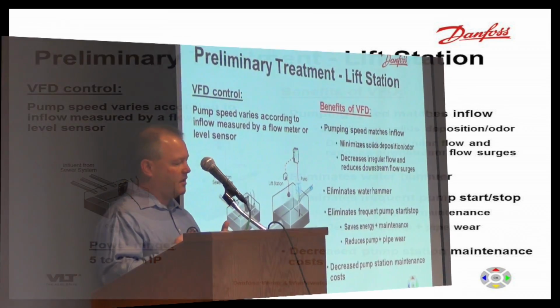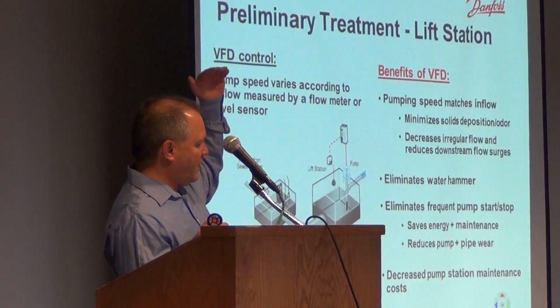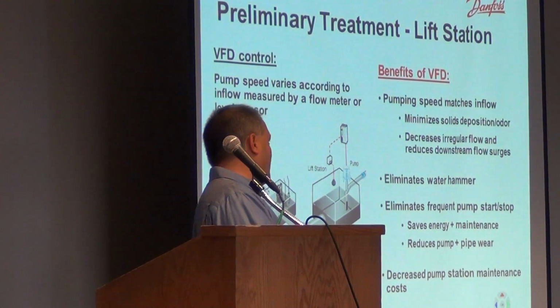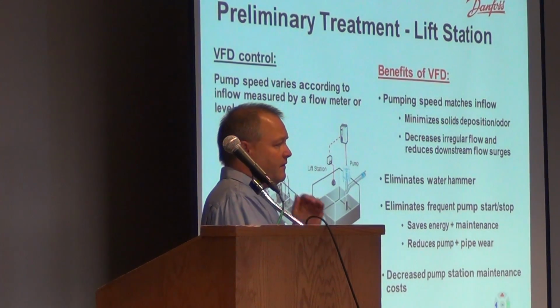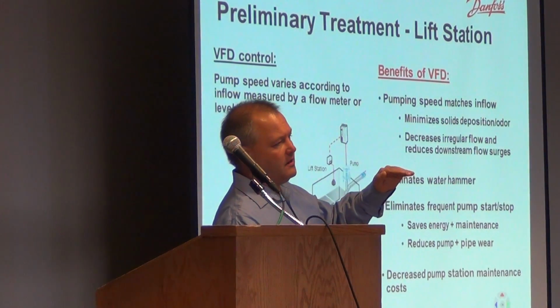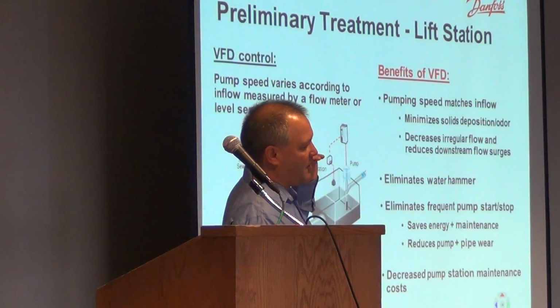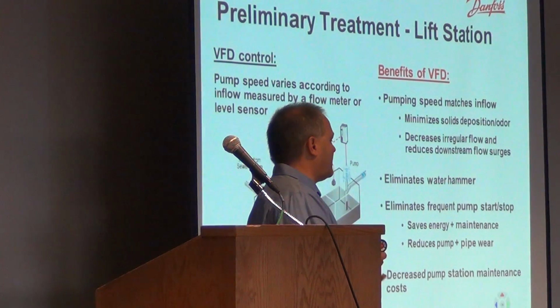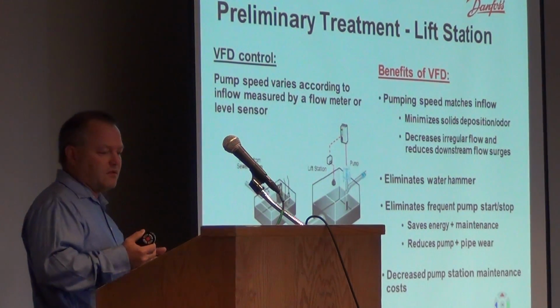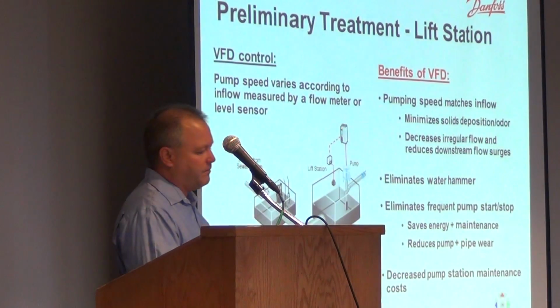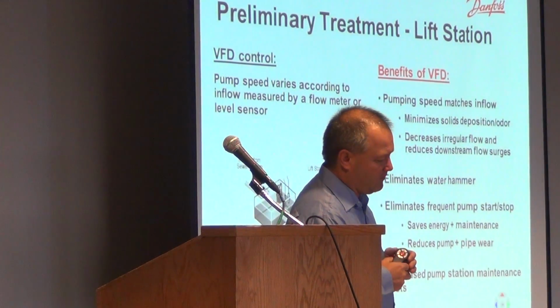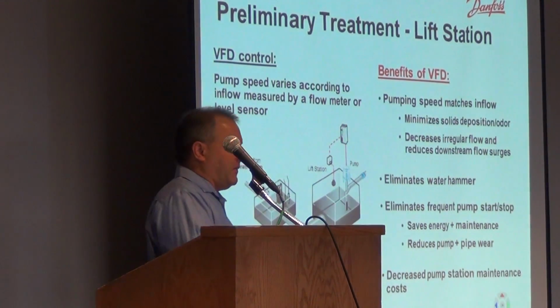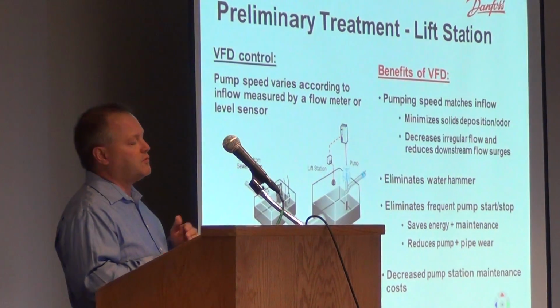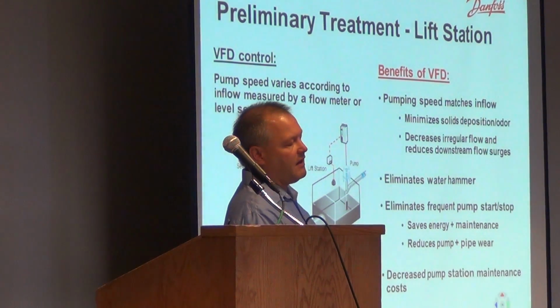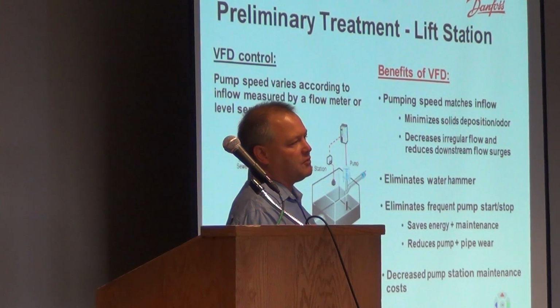A normal lift station is an on-off motor, so it slugs the system. It starts when it's at a high level and stops at a low level. With the VFD on the pump, we can actually feed the system at a continuous rate so that you're not slugging your systems. It helps with your chemicals. It helps with power consumption on the motors. If you reduce the speed of your pump motor by 10% or 15%, if it's a 20 horse motor, you're actually running at about a 5 to 7.5 horsepower motor amp draw.